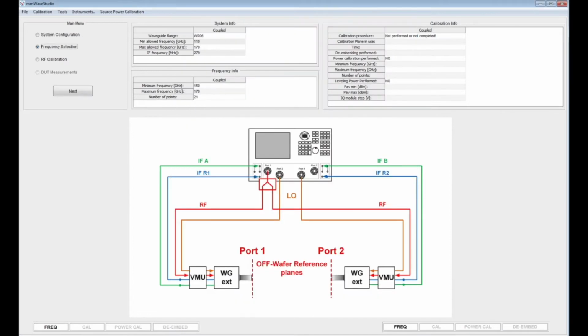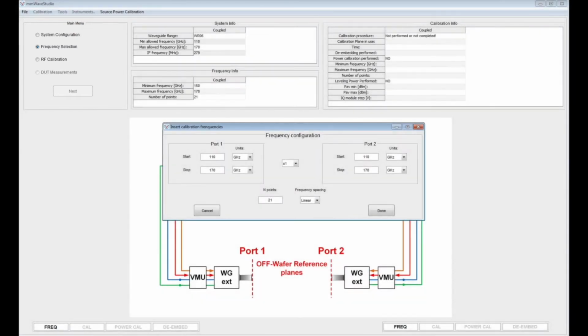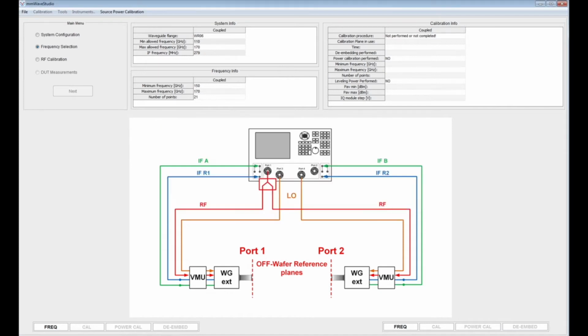The next step is to select the measurement frequencies. For that, we need to go to the frequency selection option in the main menu. Here we specify the start and stop frequencies and the number of points in that frequency range. After we have made our selection, we can click Done.